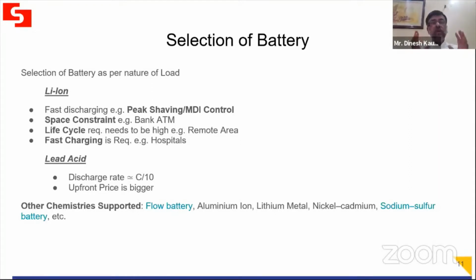For example, now in a hospital situation—when the power goes off, you want to discharge fast, and when power comes back, you want the battery to recharge immediately. How do you do that? With a lithium ion battery, because it can charge in 1 hour. And if your inverter has the juice, and your PV, grid, or DG is supplying enough power, you can charge it extremely fast. So for the next cycle, when power goes off, you can still use battery power.